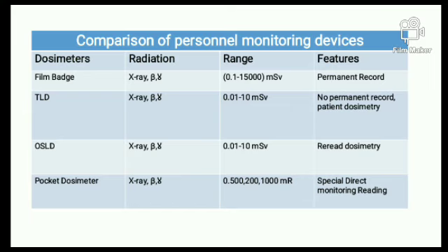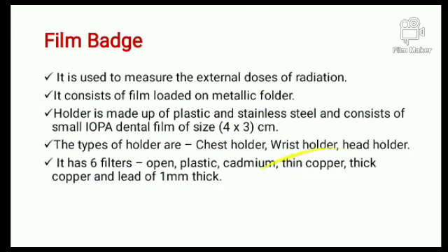So this is mainly used for measuring the instant dose of any procedure, whatever procedures you want to do at the bedside also, it is very helpful. It is used for research work as well as for calibration purposes in our quality assurance. So mainly in quality assurance we are not using the other three devices, but only the pocket dosimeter.